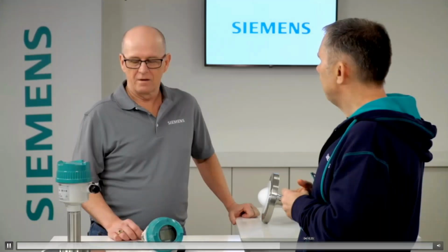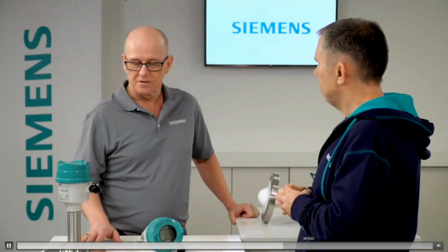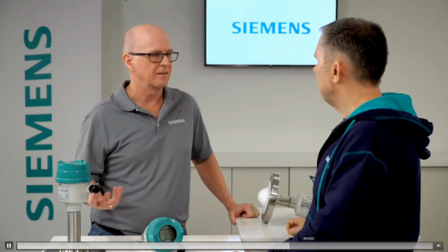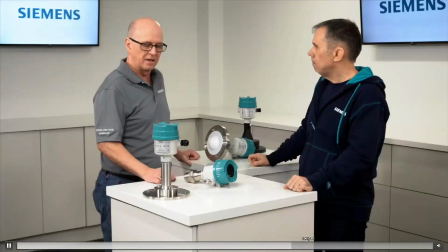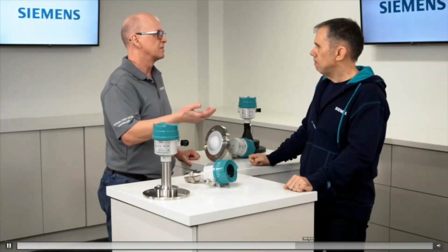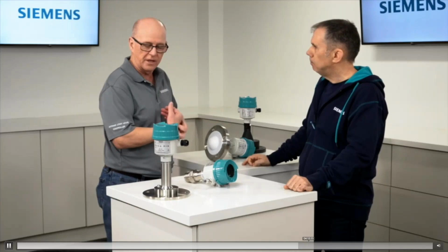Give me an example of where you would probably use those advanced diagnostics and limit monitoring particularly. Sure. In the solids applications, there's a few particularly difficult ones, flour and lime powder, for example, that tend to stick on the antenna and need to be cleaned. And today those customers are using air, quite a bit of air, for cleaning. So with limit monitoring, we can actually set a low-level limit which would drive a solenoid valve and only clean when it's necessary, thereby reducing air consumption, reducing maintenance costs on the compressor, supporting that sustainability.